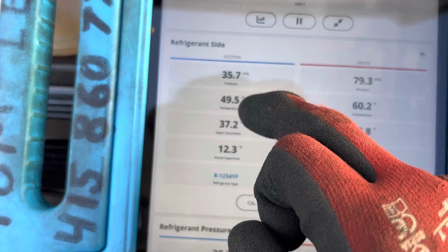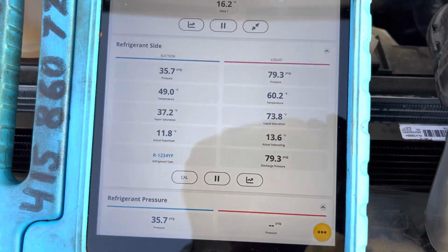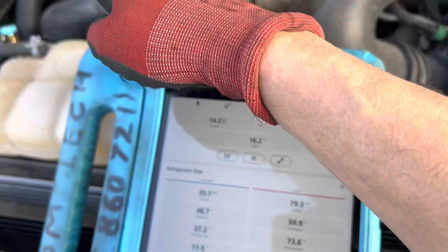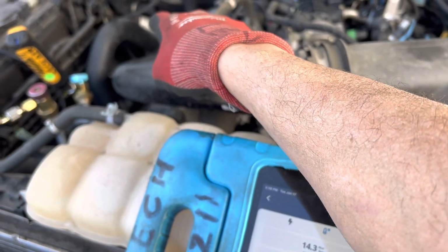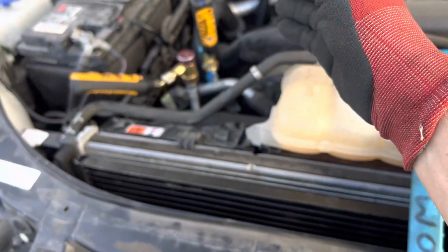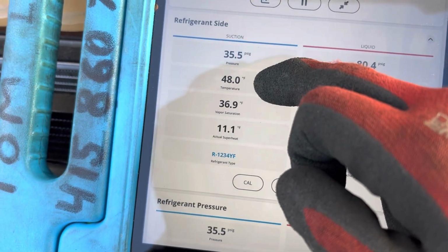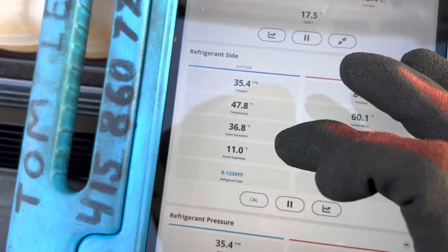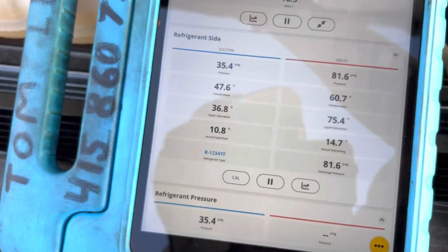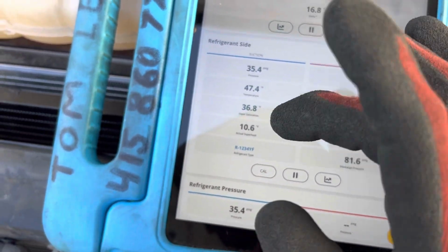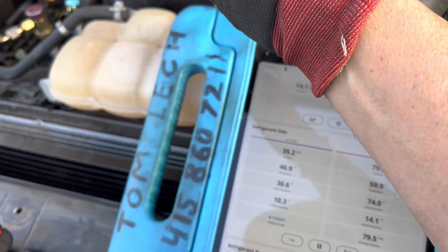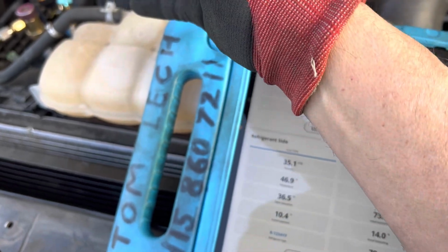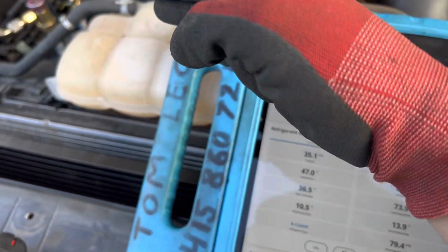So the temperature is 49 degrees at that clamp at the suction line coming out. But also coming out of there is the liquid line. So there's heat being added afterwards. So look at this, 48 degrees at that point. And at that point, it's giving us a superheat of 10. That's what you think you would have going back to the compressor. Now that's at the evaporator, but that's really not true because there's heat being added from the evaporator. It's changing the condensed liquid line. So there's an exchange of heat through the internal heat exchanger.